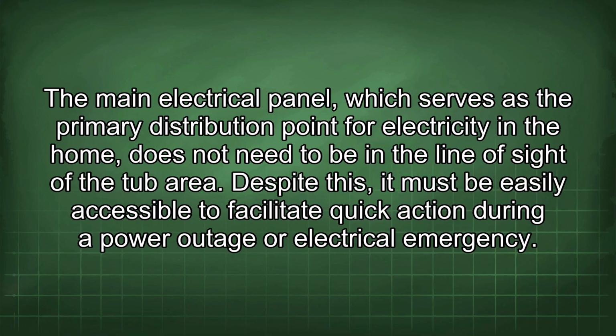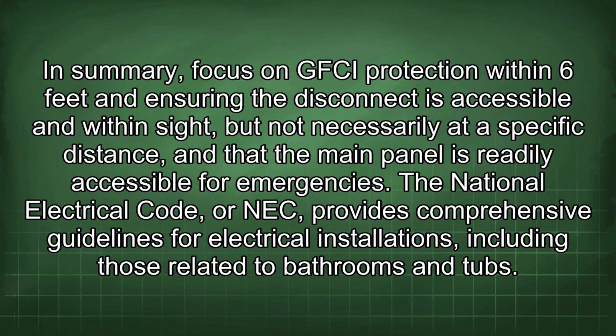The main electrical panel, which serves as the primary distribution point for electricity in the home, does not need to be in the line of sight of the tub area. Despite this, it must be easily accessible to facilitate quick action during a power outage or electrical emergency. In summary, focus on GFCI protection within 6 feet and ensuring the disconnect is accessible and within sight, but not necessarily at a specific distance, and that the main panel is readily accessible for emergencies.